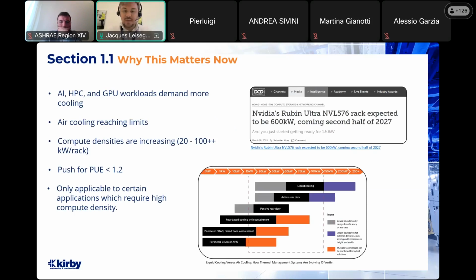The image below there is an extract from some of the Vertiv documentation, and it's a good illustration to show that as the rack densities increase, air cooling, perimeter CRAC or AHU, and raised floor solutions, even row-based cooling with containment, are reaching their limits. They're no longer a viable solution when you reach up to 75, 100 plus kilowatts per rack, and liquid cooling becomes a requirement.